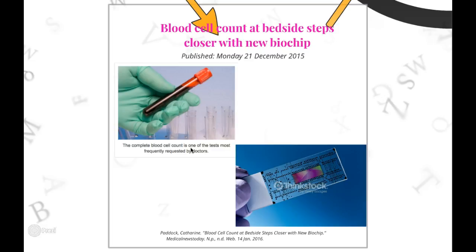Then, specific types of white blood cells, for example, neutrophils, are counted using multi-frequency analysis, which is sensitive to different membrane properties. For the red blood cell and platelet count, the biosensor uses 1 microliter of whole blood.